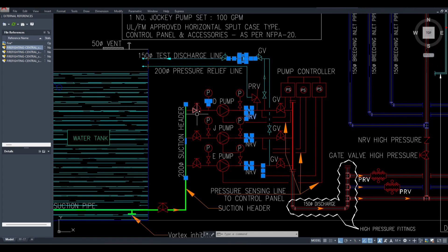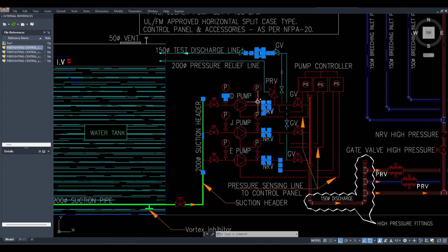But when this drawing goes to the consultant, they return you the drawings with a lot of very tedious comments - it will exhaust you to do that. And then you come back, and they tell you: maintain this distance, keep the distance between the pump, put the actual GA of the pump, provide the test line which is missing, provide this flow meter 5 diameters here and there. So what happens is it basically becomes a new design for you. Now if you are going to work, it's not a comment to implement on the model, but it's a completely whole new work for you.